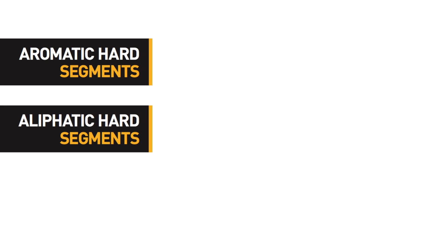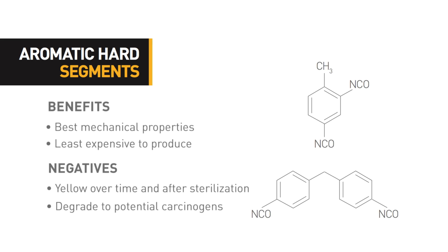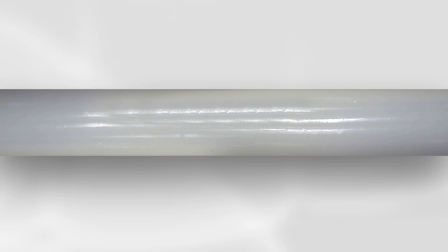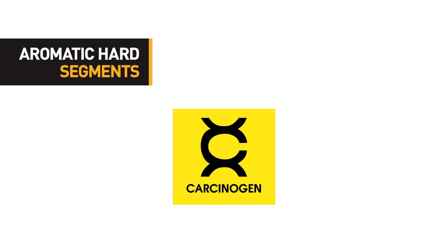The hard segment is usually categorized as either an aromatic-based diisocyanate or an aliphatic-based diisocyanate. The aromatic diisocyanates produce polymers with the best mechanical properties and are the least expensive to produce due to their low-cost manufacturing and readily available starting materials. However, when used in medical devices, the aromatic hard segments have some serious drawbacks. First, over time, aromatic polyurethanes are prone to discoloration when exposed to light, especially UV, and after sterilization. Aromatic urethanes also break down to carcinogenic diamines, so great care must be taken when choosing a sterilization technique.